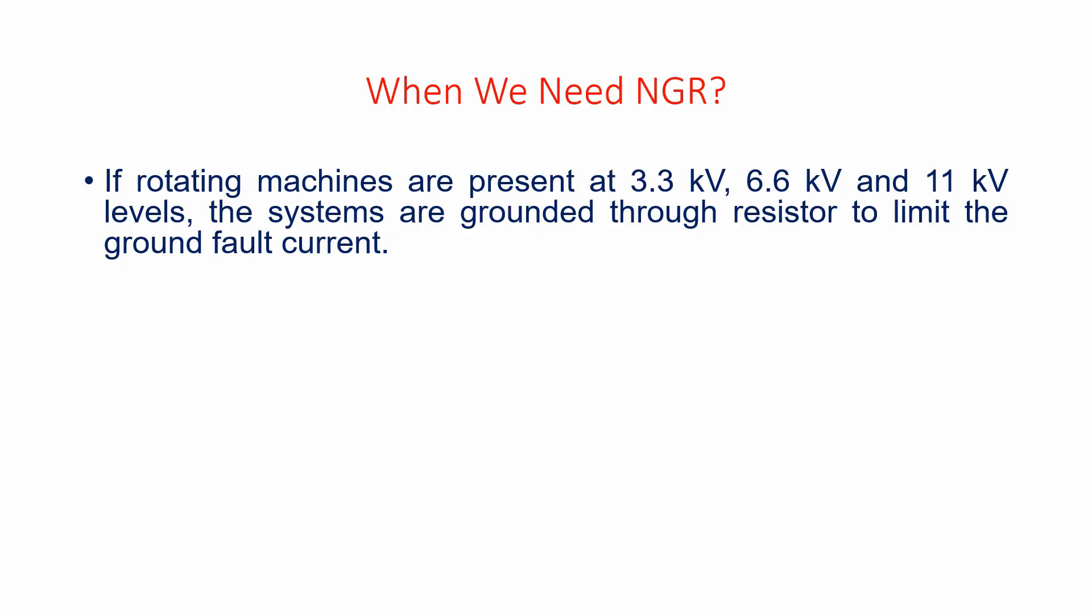In order to prevent single line to ground fault current, in fact a high amount of single line to ground fault current towards the core of motor terminals, we need NGR to limit single line to ground fault current.